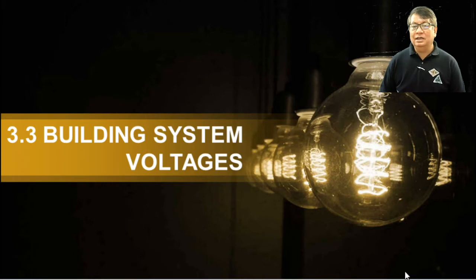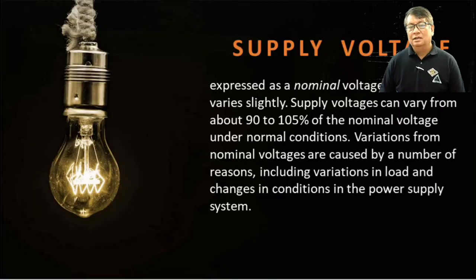Then next, we have building system voltages. So it is said that supply voltage is expressed as nominal voltage because it varies only slightly. Okay, and it will vary from 90 to 105% of the nominal voltage under normal conditions. Variations from nominal voltages are caused by a number of reasons, including variation in load and changes in conditions in the power system. So it's very clear.